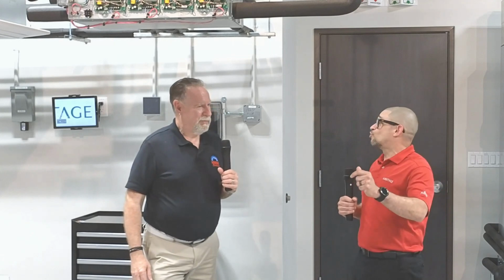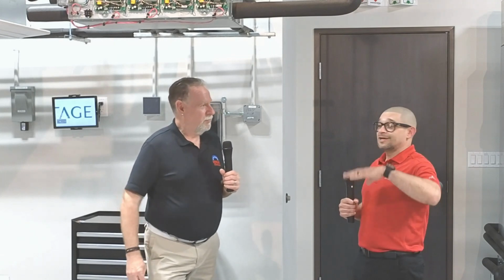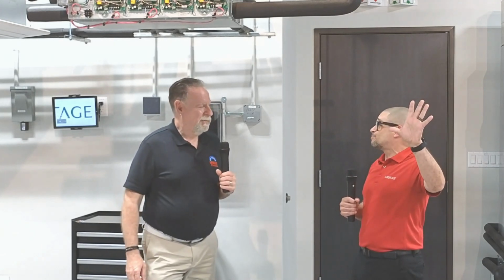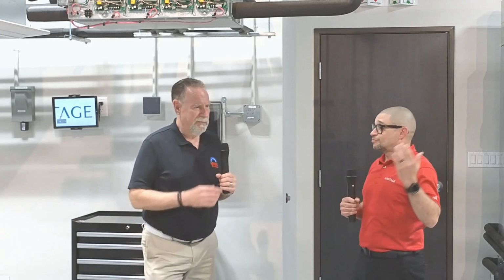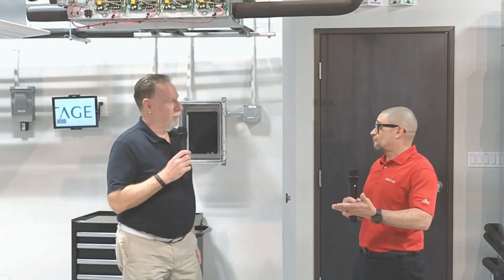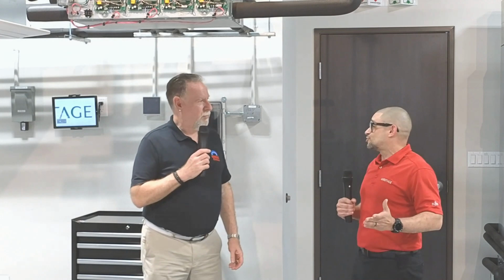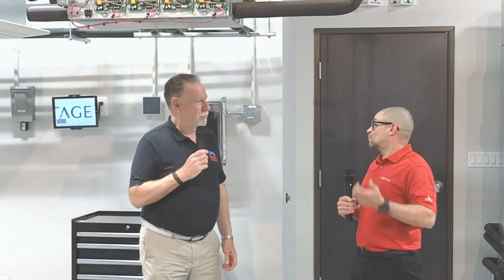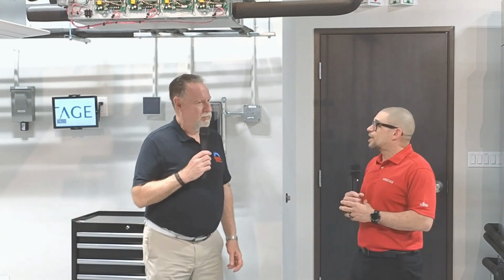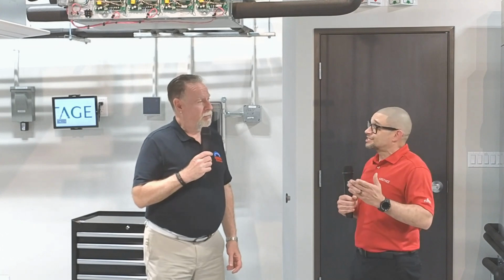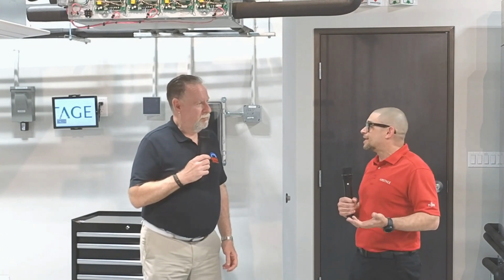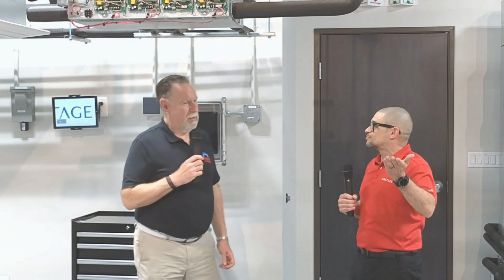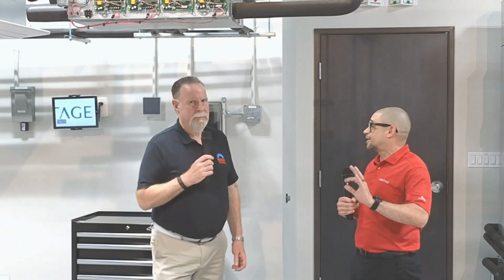Just reiterate your take on setbacks, why they might not be the best option and when they are appropriate. Before, systems were grossly oversized, so they'd cool the space down really fast. It didn't care about outdoor temperature, but VRF systems do consider outdoor temperature to perform correctly. They manage refrigerant flow, not sending it where it's not needed, so you're always saving more energy. Doing setbacks on a VRF isn't recommended because it'll use way more energy to bring the temperature back up, when you could just set it and forget it.